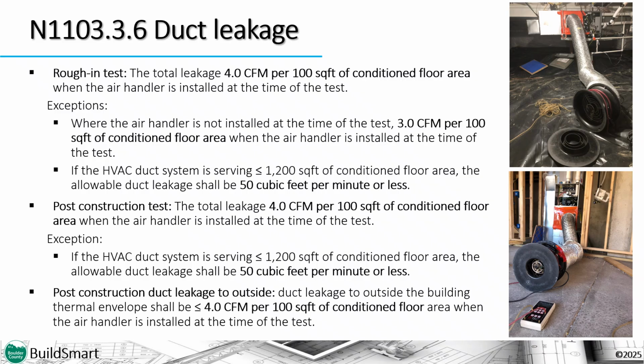If the system is tested at a rough stage of construction and the air handler is not installed yet, both the return and the supply side of the system must be tested, and together they can't leak more than 3 CFM per 100 square feet of conditioned floor area served. For a 2,000 square foot house, for example, the system cannot leak more than 60 CFM of air in this case. If the system is being tested post-construction, the 4 CFM target is used, and if the home being tested is 1,200 square feet or less, you can use the exception that is stated on this slide. Lastly, the duct leakage to outside test used in the energy modeling software for the HERS Energy Rating Index compliance approach also uses the 4 CFM compliance target.